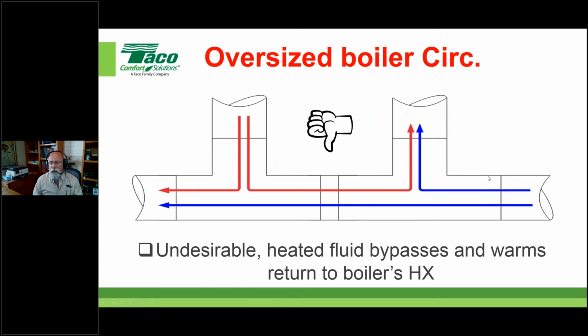Now I'll admit that under these shoulder conditions, these bench conditions where it's not really cold, just kind of sort of cold, maybe in the spring and fall, you're going to get this a little bit because, as I said before, even if you have a circulator controlled by the boiler, you can't go any lower than low. What we have going for us in those shoulder conditions is that they're nowhere close to a design condition, and they're relatively short periods of time where we have this. The cumulative temperature is still below that magic number of condensing, so I'm still condensing for the most part within those shoulder conditions.